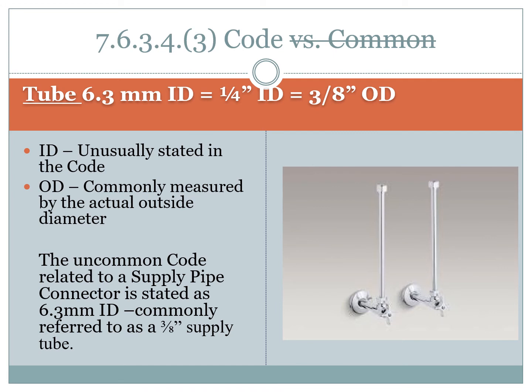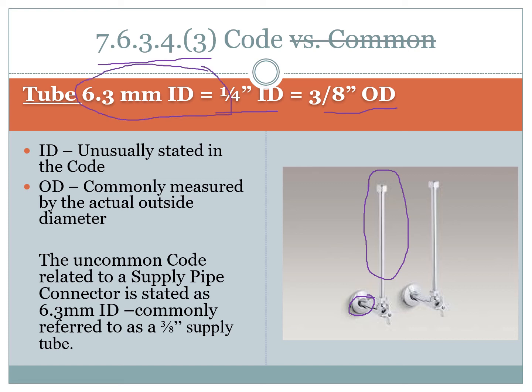On the job you'll often have what we call a 3/8 riser tube — but that's not what this code is talking about. The 3/8 minimum size is the pipe that comes out of the wall. The riser tube is captured in section 7-6-3-4-3, and it actually specifies quarter-inch inside diameter — 6.3 millimeters inside diameter, which is a quarter inch. It might be 3/8 OD, but the code states the inside diameter. Don't get those things confused — just trust those tables.